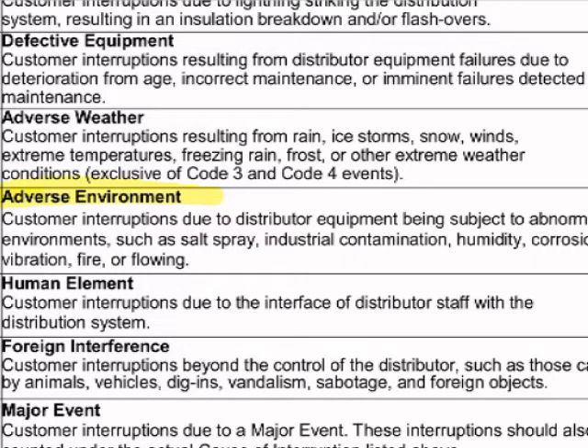Adverse environment's one that we don't tend to see so much around here in this part of Ontario, generally due to unusual environments. So around here we'd see it if you had assets like a pad-mounted switchgear or an underground system right along a roadway that was heavily salted. All that salt starts working its way into the equipment and causes corrosion, and that corrosion results in a failure or tracking across the surface because salt water is incredibly conductive of electricity, and then you get an insulation breakdown and off she goes. You can also get similar effects if you end up with an excess of pollution. Some types of pollution and ash can end up being fairly electrically conductive, and if you get enough of it on the surface of your stuff, it can cause tracking and electrical conduction to begin occurring over the surface of your insulators, resulting in a fault.